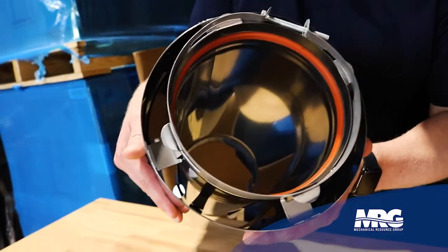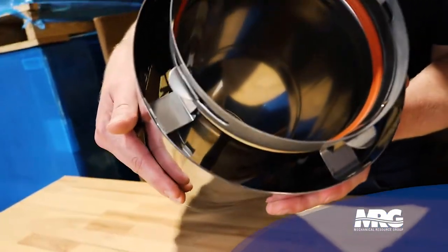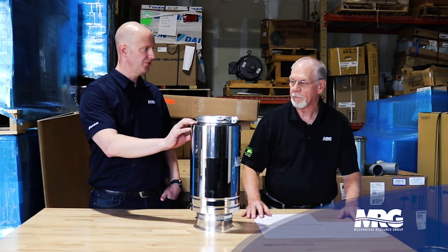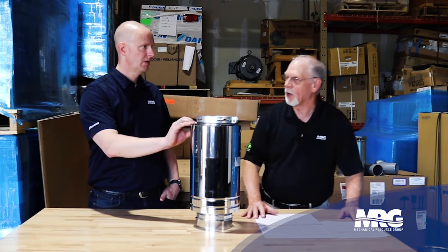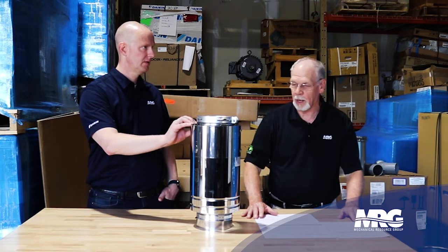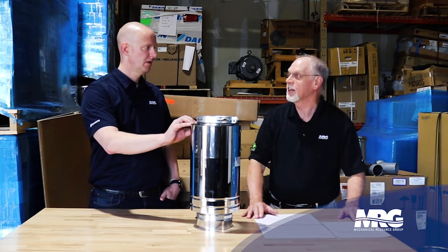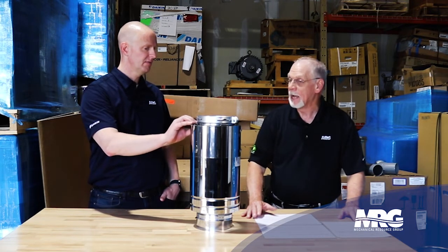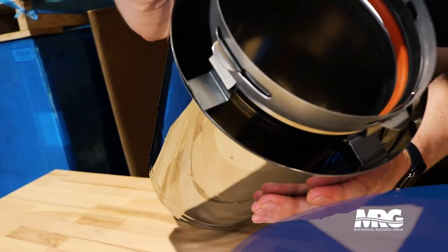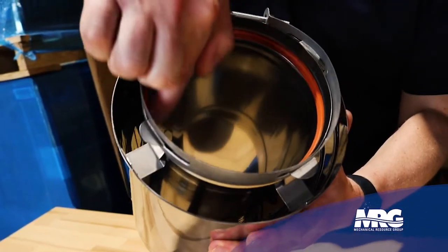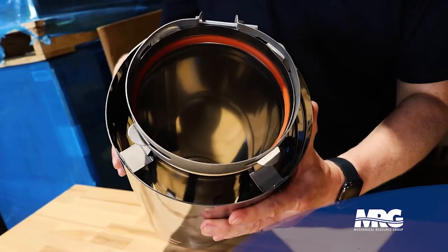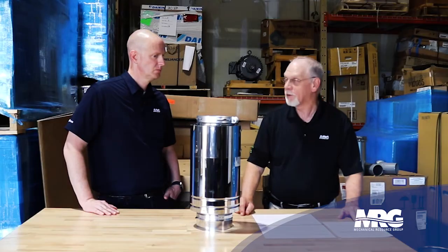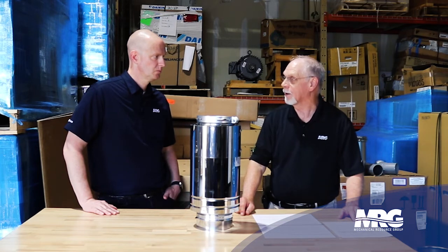That AL29-4C, is that just for the anti-corrosive? Yeah, it's a special compound of the stainless, which will stand up to that acidity. Exactly. And this also has rubber joints so that you have a good seal, because it's going to have water inside of it, and that water is going to be coming back to the low point, so we have a collector for the water to take it and neutralize it and take it to drain.